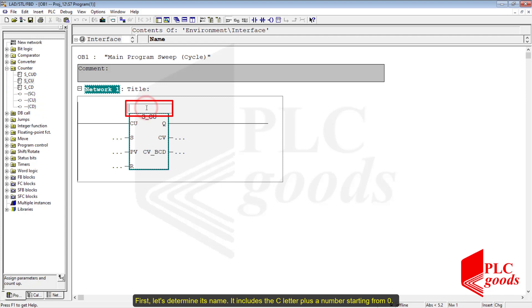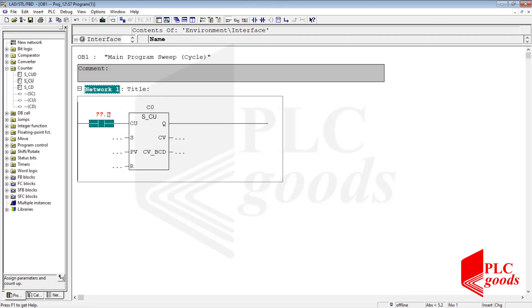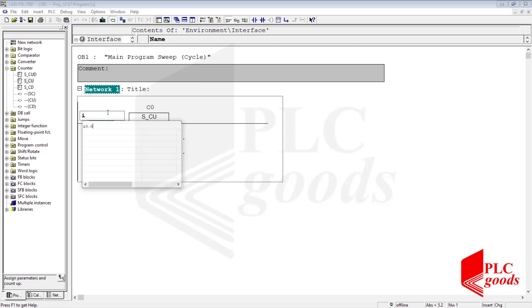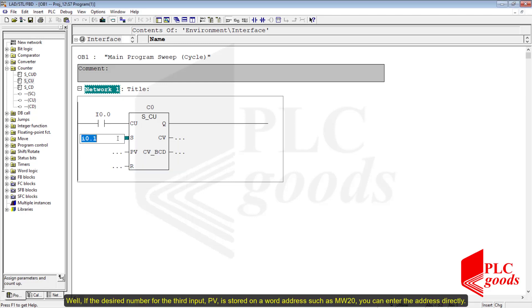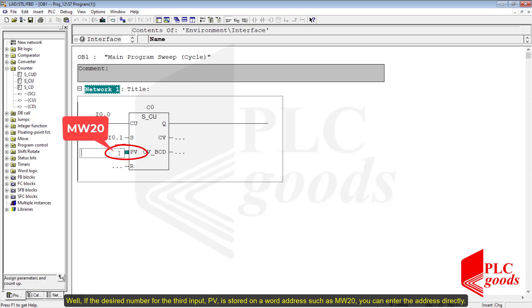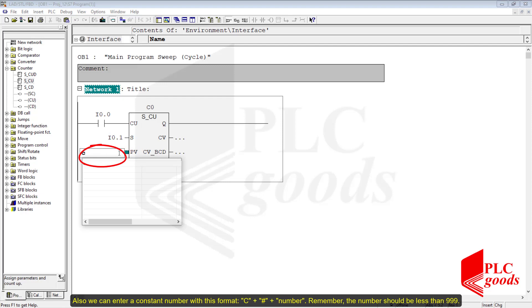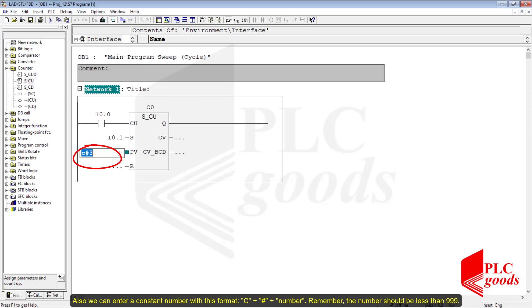Let's determine its name — it includes the C letter plus a number starting from 0. If the desired number for input PV is stored on a word address such as MW20, you can enter the address directly. We can also enter a constant number with the format: C plus the hash sign plus a number. Remember, the number should be less than 999.